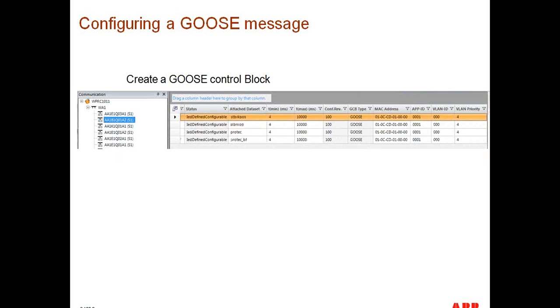The next step is I need to create my GOOSE control block, or the GOOSE control block that this relay is going to use to publish or to send this information. And I'm creating it here. I define my different parameters, Tmin, Tmax, define that this is a GOOSE, define the destination MAC address, application ID, virtual LAN, and VLAN priority as adequate.